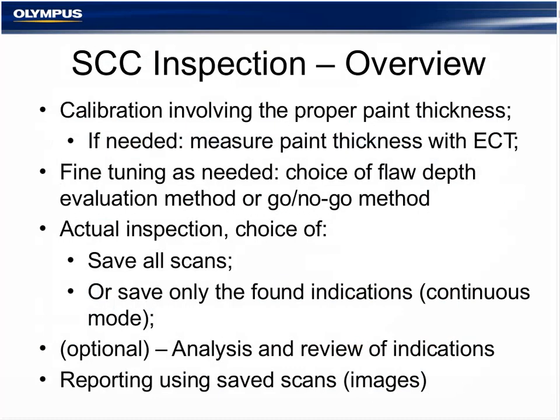As an overview of the steps that this person has to do from A to Z: A is the arrival on site and Z is the report. Minimal surface preparation would count for basically wiping the pipe surface, making sure there are no bird droppings or anything that would prevent the probe from scanning smoothly. But that's as far as it goes. The calibration involves having the proper paint thickness on the standard, and if needed, it's always possible to measure that with ECT. So the same instrument could do both, the paint thickness check and the actual inspection. Fine-tuning as needed and a selection of the method, we are going to see that. And that's it, it's ready to inspect.